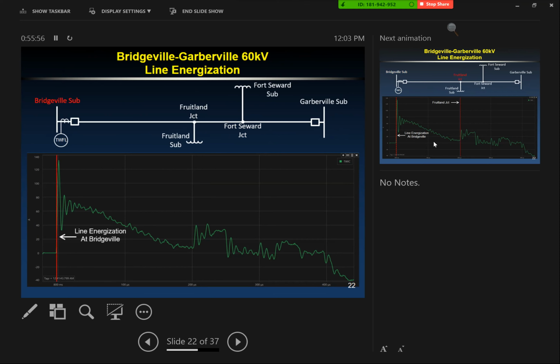Then we would go to GIS and figure out what is the actual mileage, the distance from Bridgeville Sub to that fault location, or what's the whole number. So for this line energization event, let's look at the first point of interest. This is when we would close Bridgeville Sub to energize the line, with Garberville open. This first spike represents the traveling wave you launch when you close that breaker, and it's the current traveling wave, about 140 amps.